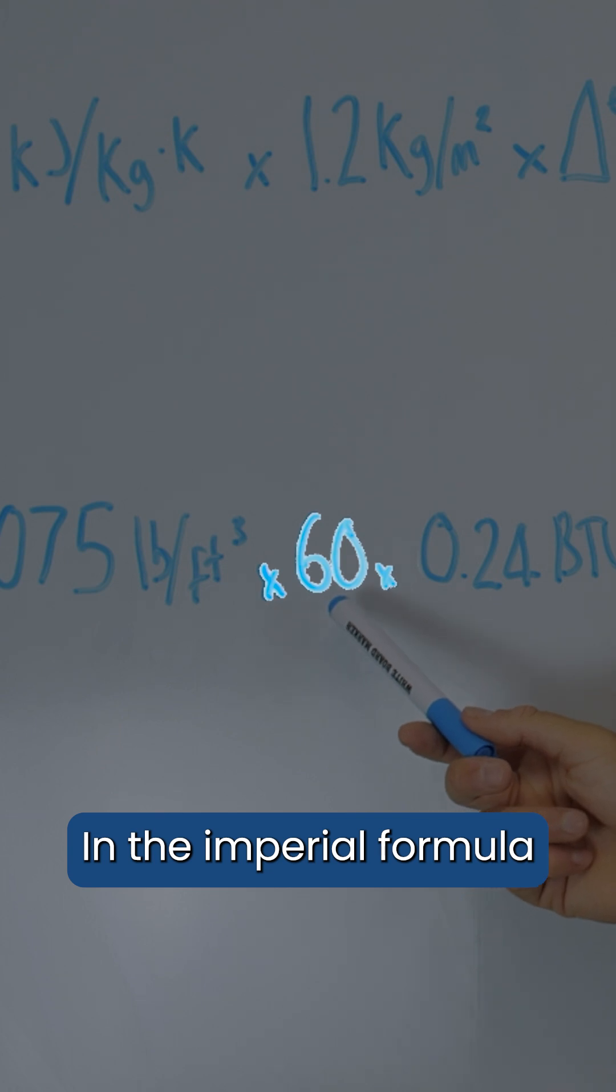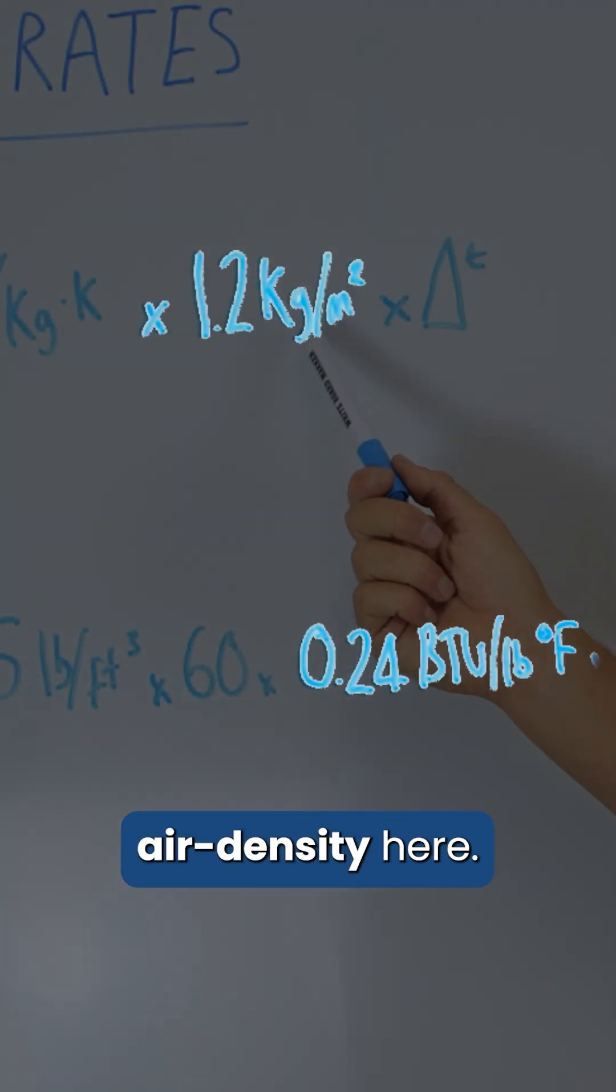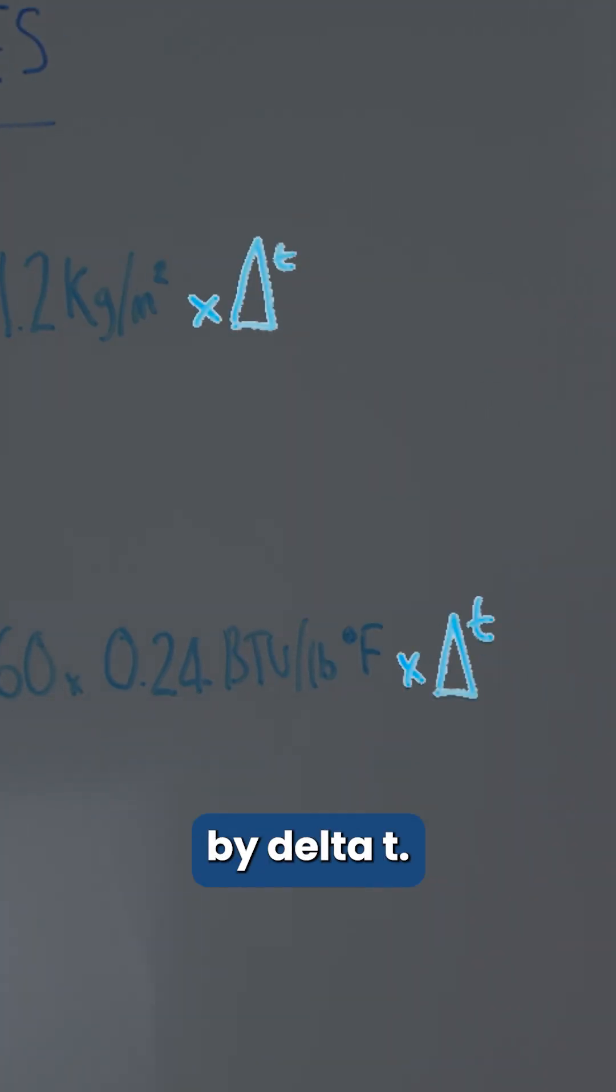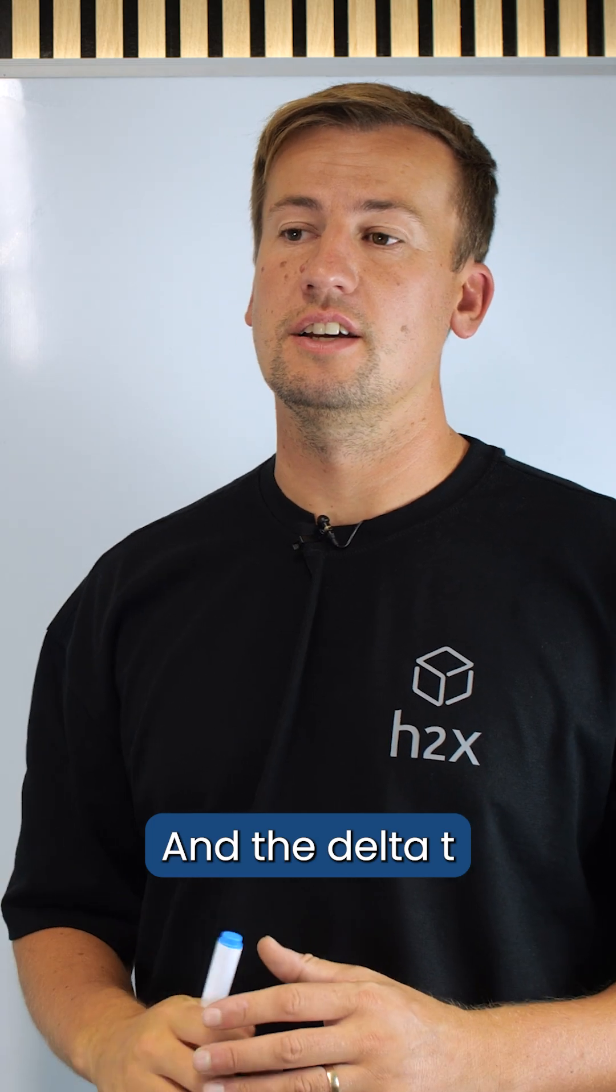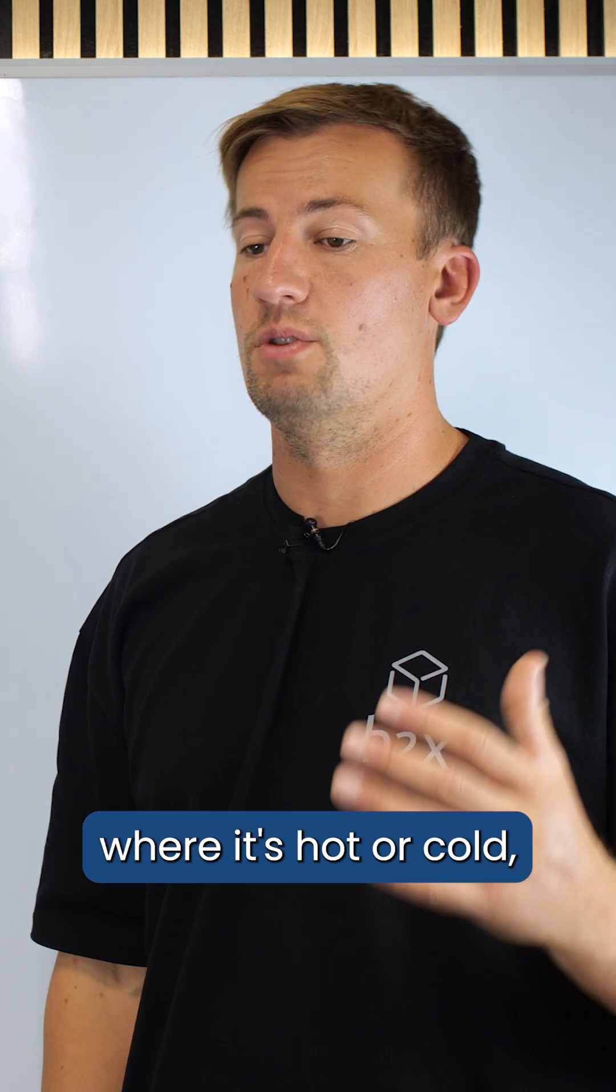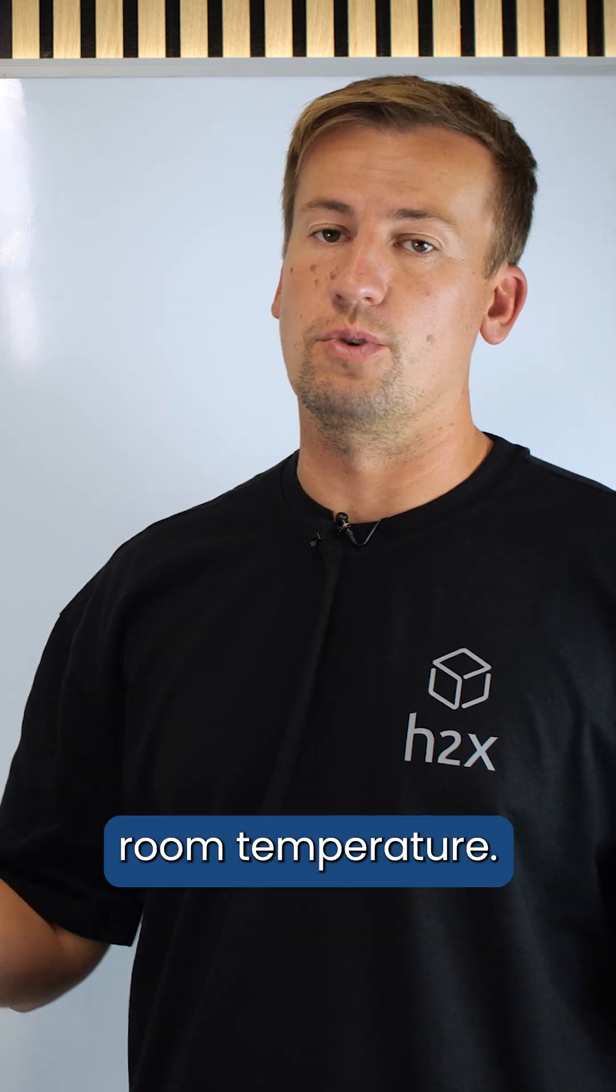In the imperial formula there is a multiplication by 60 to go from minutes to hour that's not in the metric one, and then we have the air density here, and the final part is the multiplication by delta t. And the delta t is the difference between the supply air temperature, whether it's hot or cold, and the room temperature.